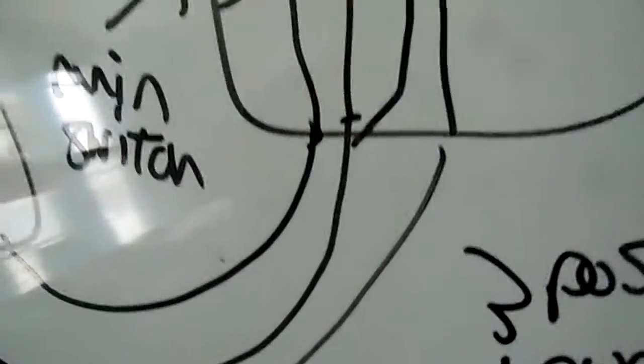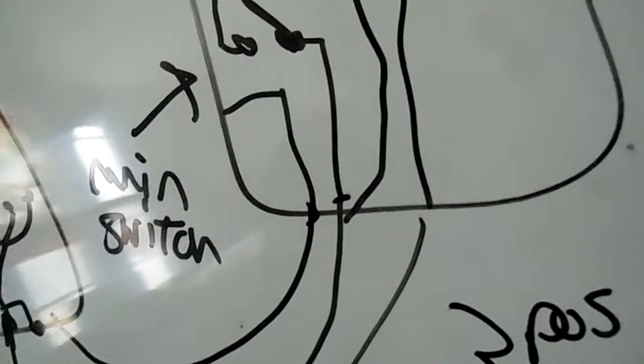Then that's the same thing on the other connection. But that comes straight down the line, the 18.8 kilovolt. But for reference, 1 kilovolt equals 1,000 volts. Then that steps it down to 440. That's carrying about 1,600 amps on the commercial side, but the residential is carrying 16.6 kilovolts at 800 amps.